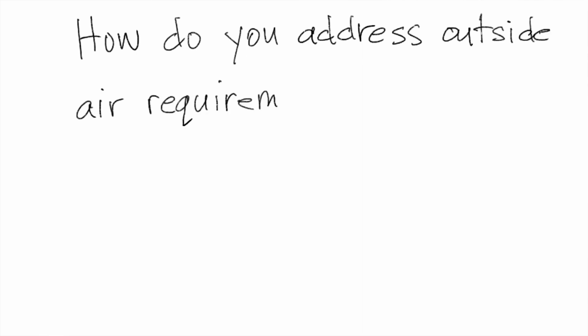Next question that I got was, how do you address outside air or ventilation requirements? How do you address introducing outside air or ventilation in a historic or in existing buildings? This is one of the most common questions that I get when it comes to VRF. Depending on where you are, here in California, there's local code that requires a certain amount of outside air to provide fresh air ventilation into the space, depending on how the building is used. And how do we do that? The easiest way to do that is with a separate DOAS, or dedicated outside air system, whose only job is to bring in outside air, temper it, and then bring the outside air and distribute it through the inside space.